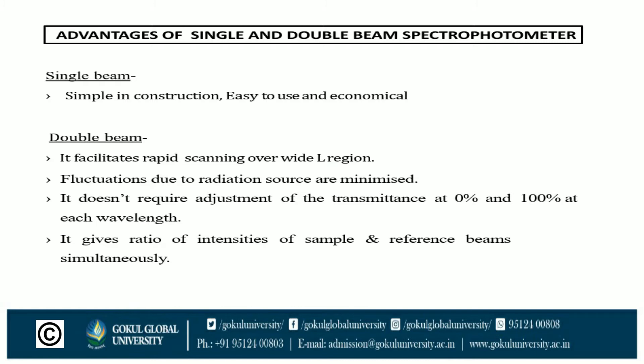The double beam does not require adjustment of the transmittance at 0% and 100% at each wavelength, whereas in the single beam, adjustment at 0% and 100% is required every time for each wavelength. The double beam gives the ratio of intensities of the sample and reference beams simultaneously, providing sample and reference results at the same time.